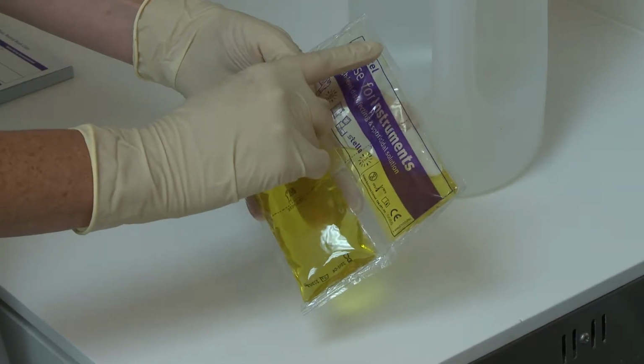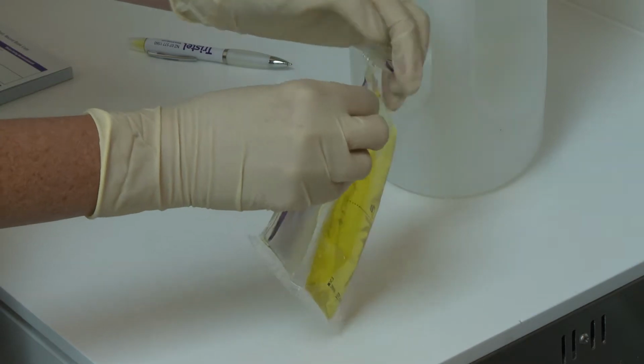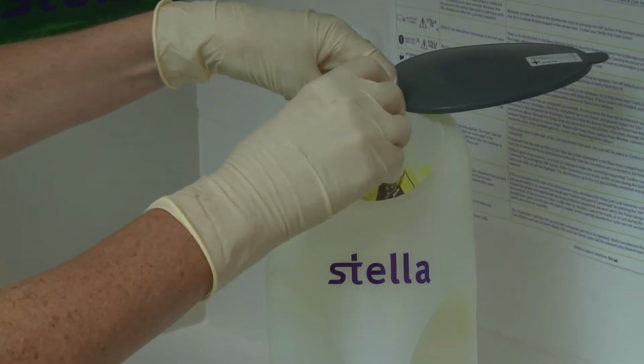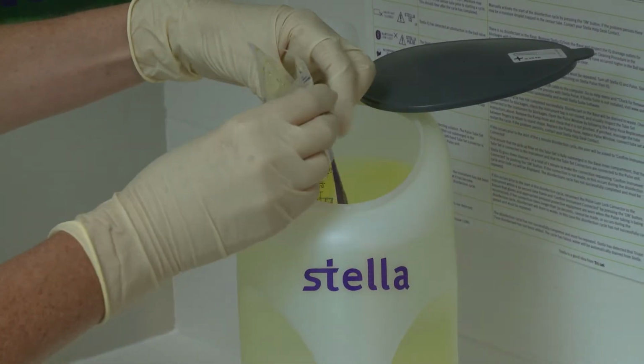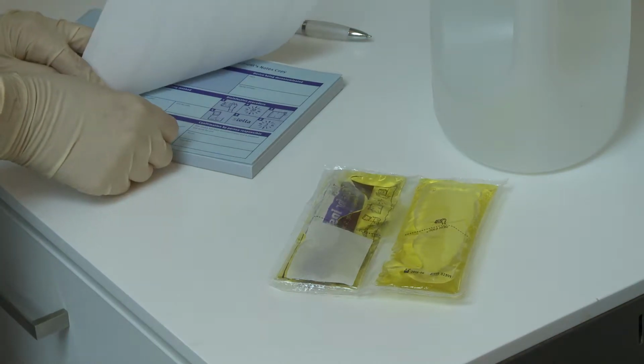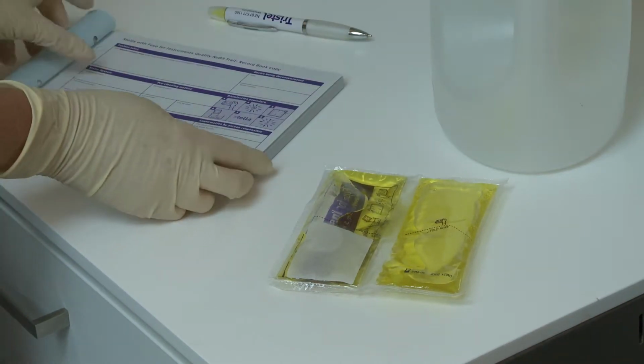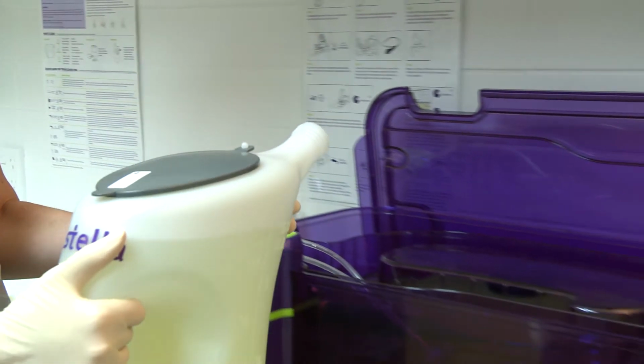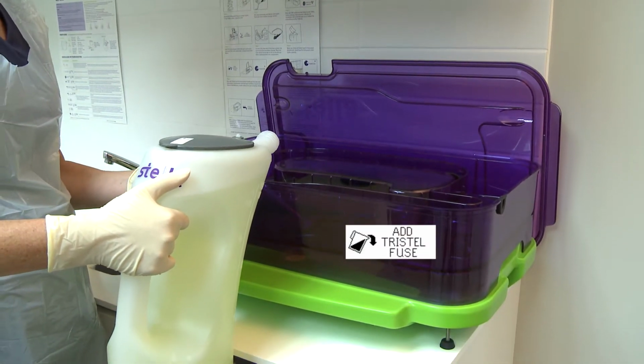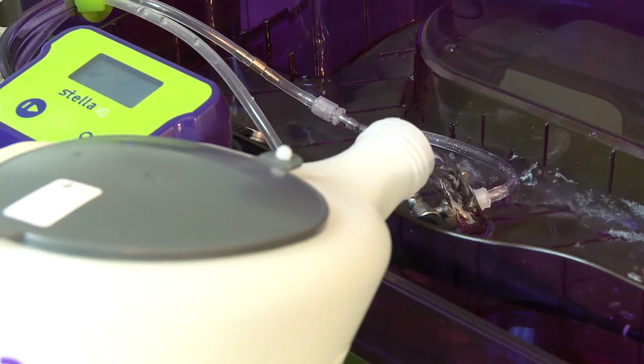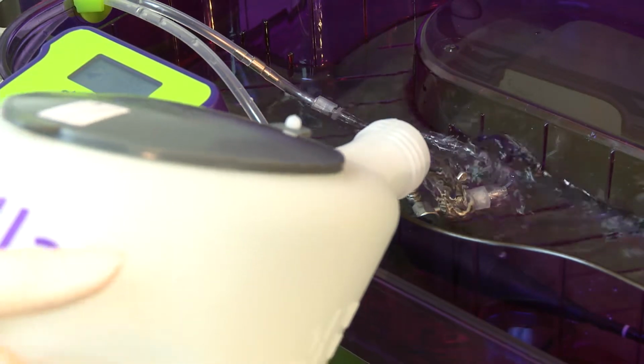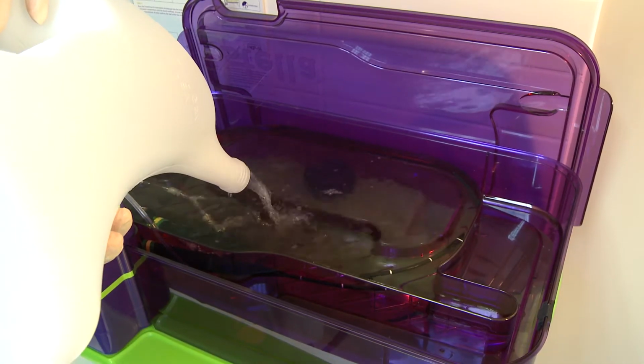Cut the corner of the sachet. Pour the contents into 5 litres of water. The sachet has 2 labels for each copy of the audit trail. Stella IQ will direct you to add Tristel Fuse for Instruments. Pour all 5 litres into the inner compartment until the liquid overflows.